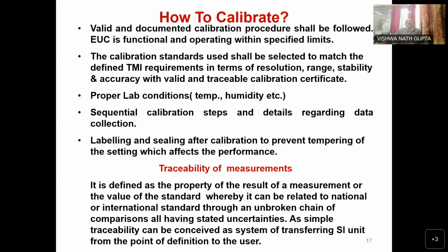Sir, here I would like to give one example. When I was in BHEL, on the test bed of a 500 megawatt thermal generator, this was such a huge generator, and its winding has very low resistance. That means measuring it also gives a very challenging problem. So what happens, sir? Everything was accurate, but the measurement of the winding resistance was giving slight variation.